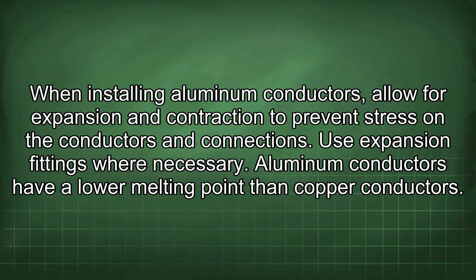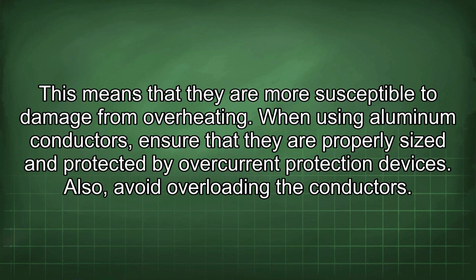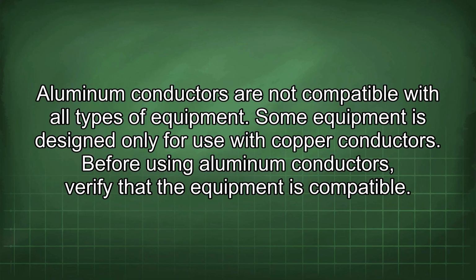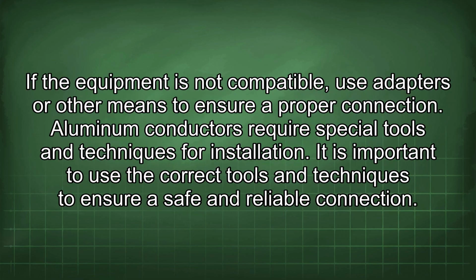Aluminum conductors have a lower melting point than copper conductors. This means that they are more susceptible to damage from overheating. When using aluminum conductors, ensure that they are properly sized and protected by overcurrent protection devices. Also, avoid overloading the conductors. Aluminum conductors are not compatible with all types of equipment. Some equipment is designed only for use with copper conductors. Before using aluminum conductors, verify that the equipment is compatible. If the equipment is not compatible, use adapters or other means to ensure a proper connection.